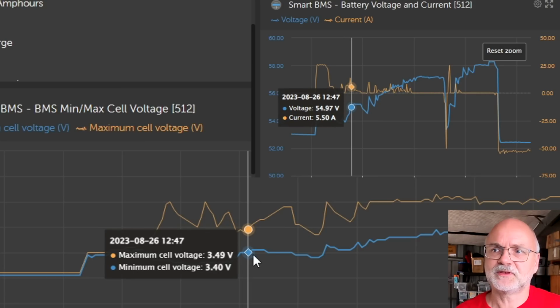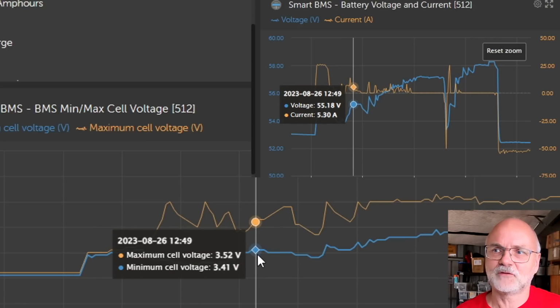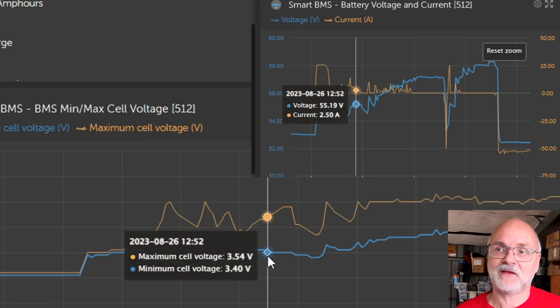So if we charge a bit higher, to 55, 55.2 volts - this was our maximum charge voltage at the beginning when we did the capacity test - we can see the cells spreading apart now, 3.54 to 3.40.